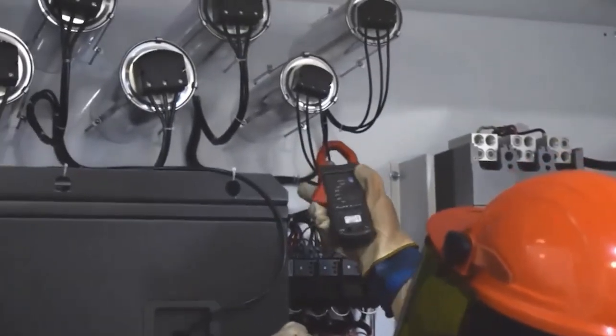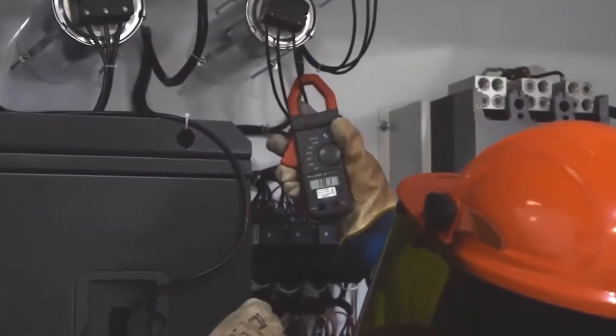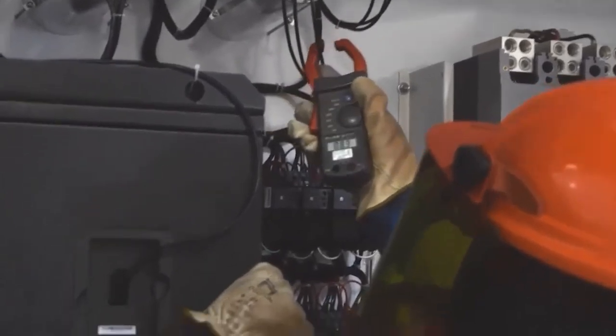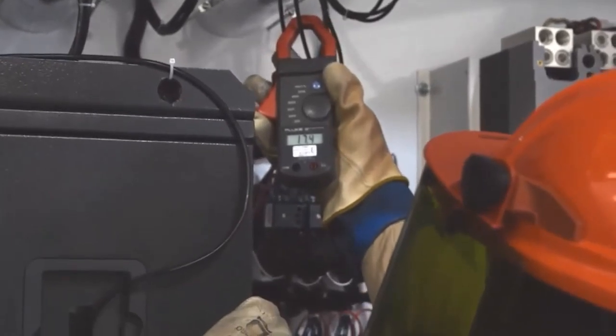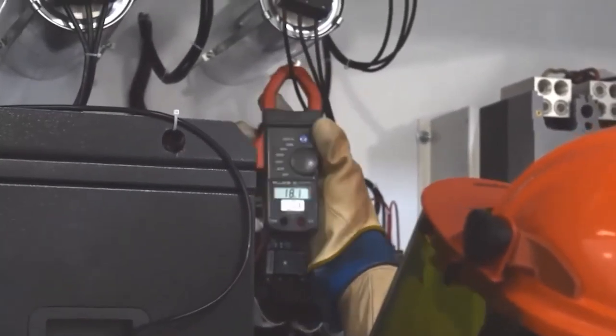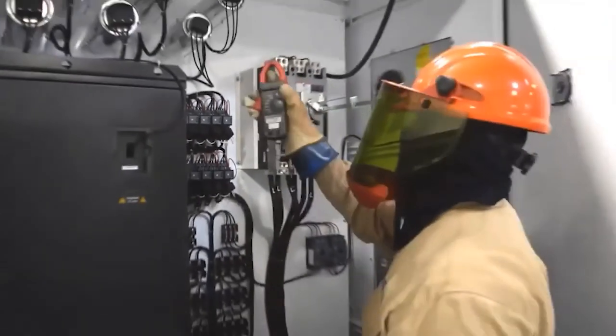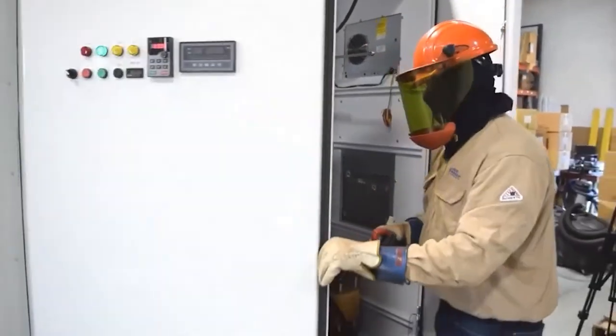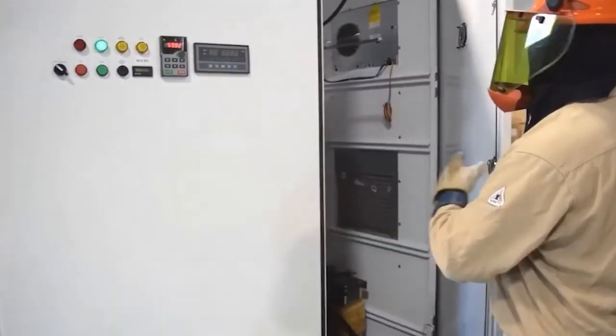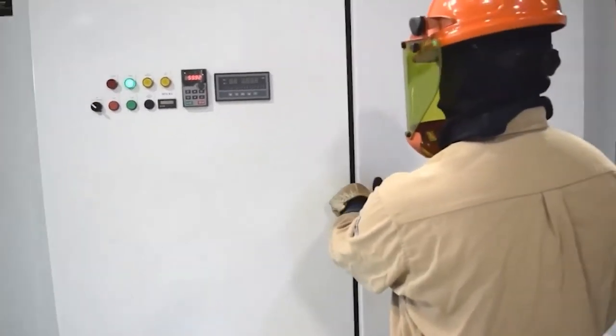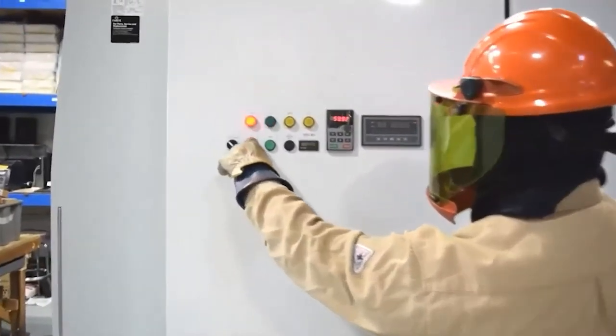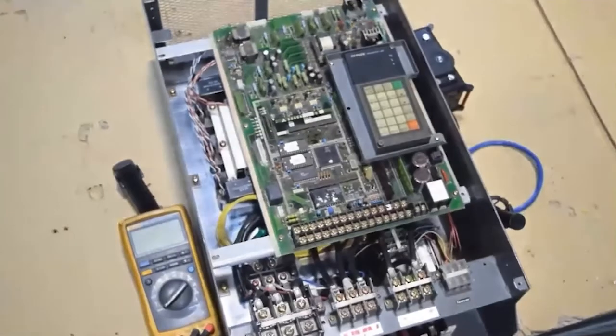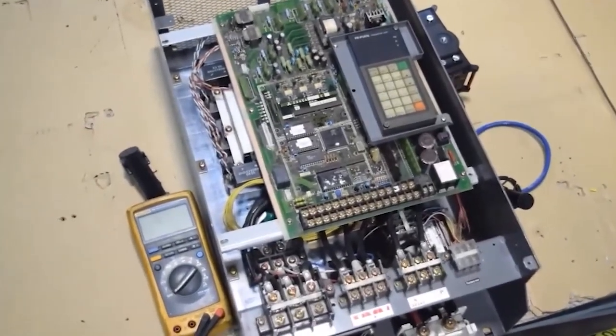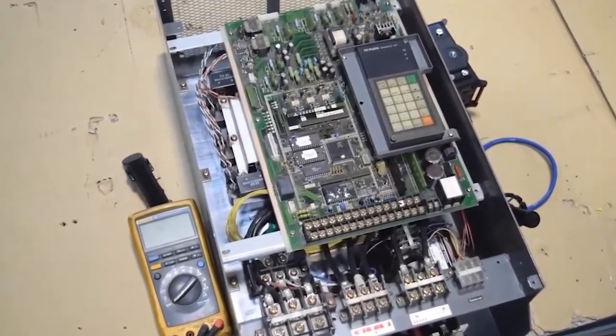So now I've got a clamp-on meter, and I'm going to measure my capacitors. This is another test that can be done. You notice I'm getting about 18 on it. So your capacitors, when operational, should have about the same current on all 3 phases, not voltage, I apologize. You'll go ahead and measure all the capacitors that same way. And once again, the higher kVAR capacitors are going to have a higher current reading. But when you're measuring from A to B to C, they all should be the same on the same capacitor. All right, I want to pause.